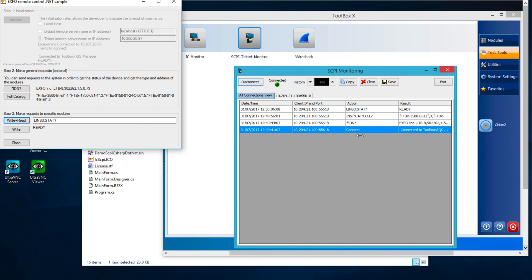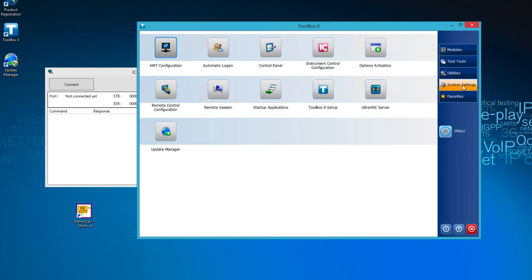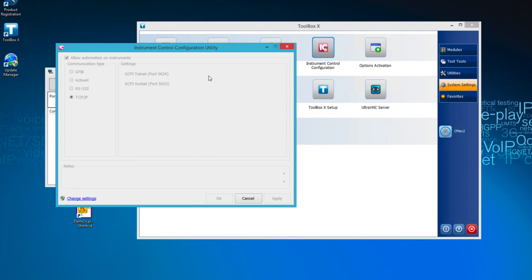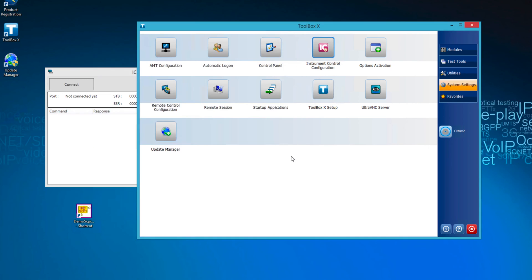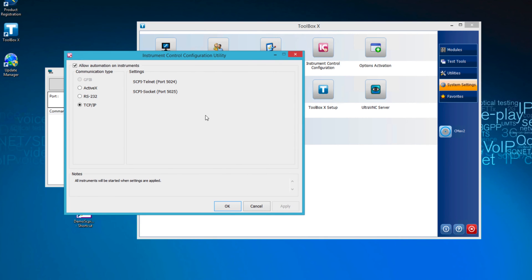You could install the demo SCPI C-Sharp .NET application directly on the LTB-8. In this situation, you could use the ActiveX method of control. Take note that in this case, you would need the other SCPI monitoring tool from the EXFO toolbox. Its name is IC Monitor and is available in the Test Tools tab. You would also need to change the instrument configuration to ActiveX.